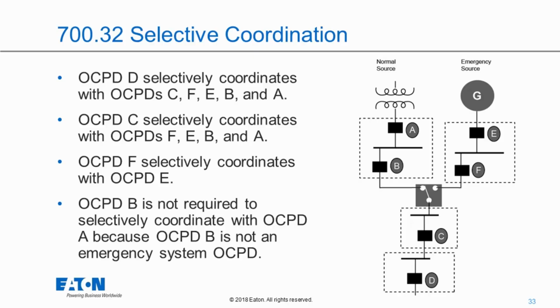And often, for those of you who have done selective coordination studies in the past, you'll know that the most challenging part of the coordination is often through the normal source. What makes selective coordination very challenging is fault current. If I have more fault current, then it can be more challenging for some types of overcurrent devices. The higher fault currents are going to come from the utility, and so that's why the real critical path there is to make sure we have selective coordination with the emergency system devices and the normal source devices.